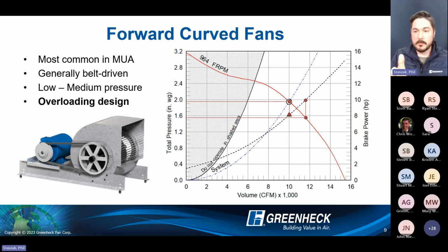So at original selection, we were at 8. Probably felt pretty confident laying that system out with a 10 horsepower motor. Well, now you're right at the FLA or the overload state of that fan. So now good luck even getting an air balance done to calculate that you're just under 12,000 CFM to dial that system back with that static pressure not being present. So it risks an overload state.